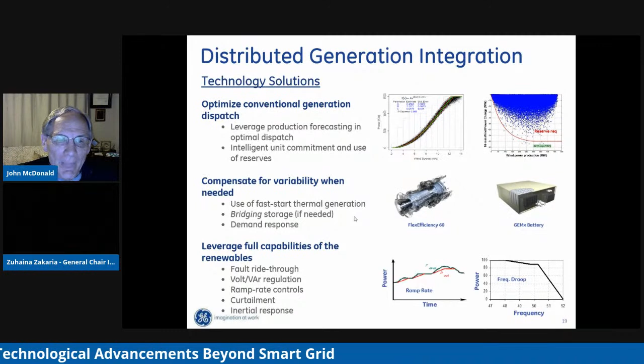In fact, a couple of years ago, GE announced a new electric hybrid gas turbine, an integrated system with 10 megawatts of lithium-ion batteries and a 50 megawatt fast start, fast responding natural gas fired turbine generator, with software that optimizes the operation of the two integrated together. It's very nice because it can respond instantaneously with the lithium-ion batteries, but also respond to longer duration needs with the turbine generator, which can recharge the batteries. It's a very optimal operation of the two working together.